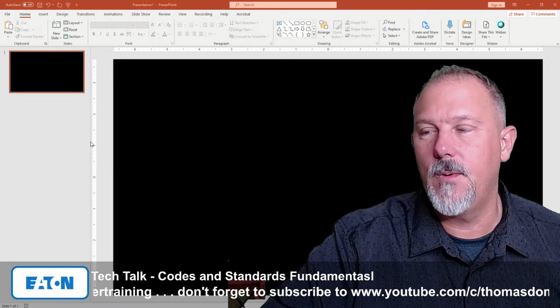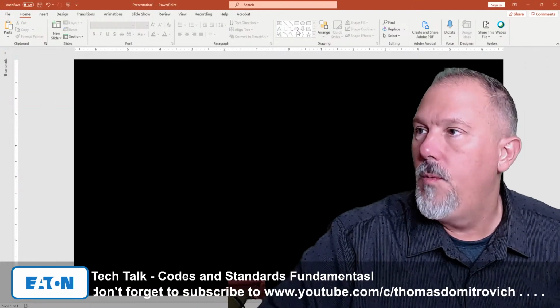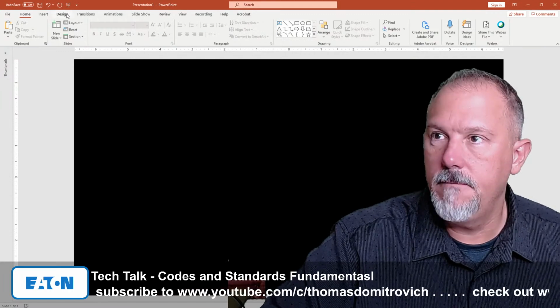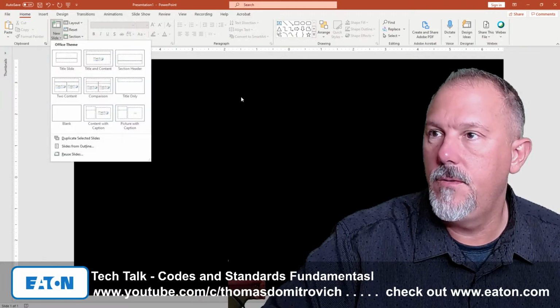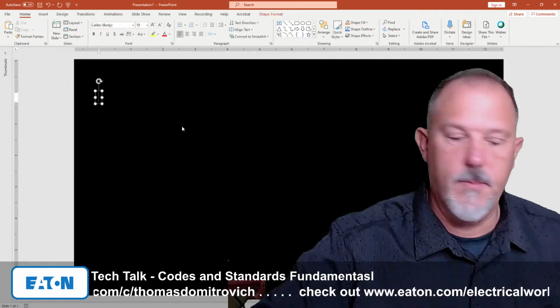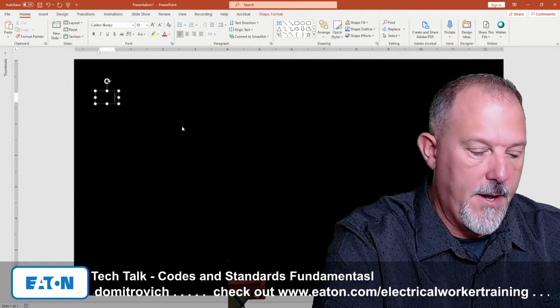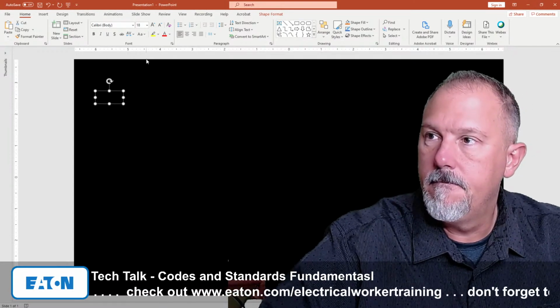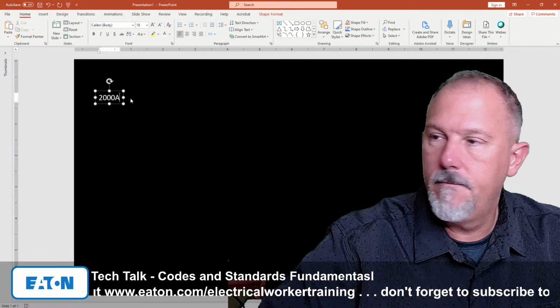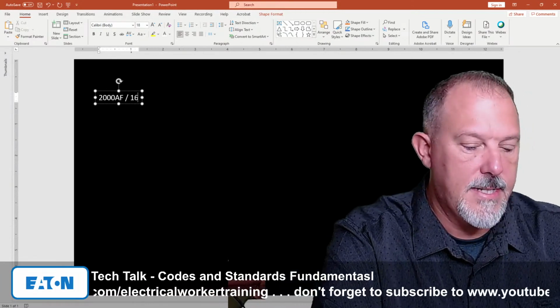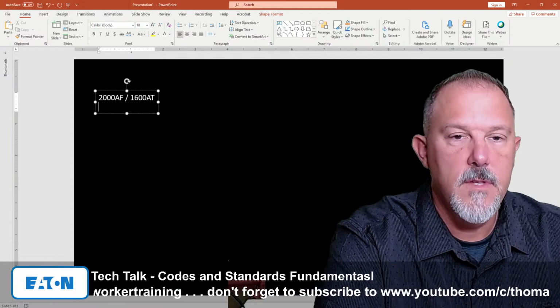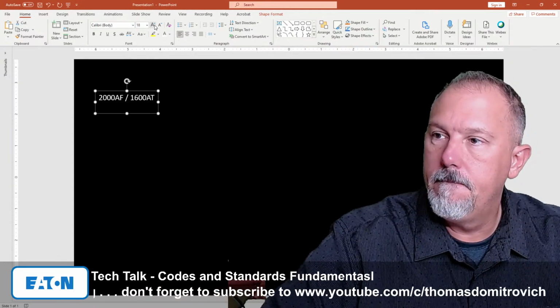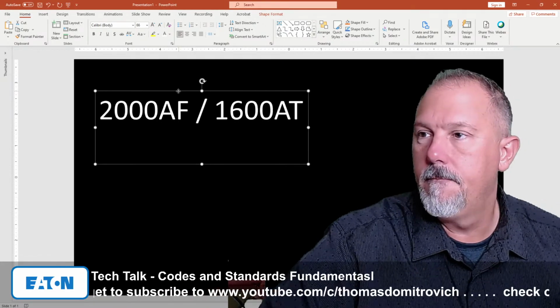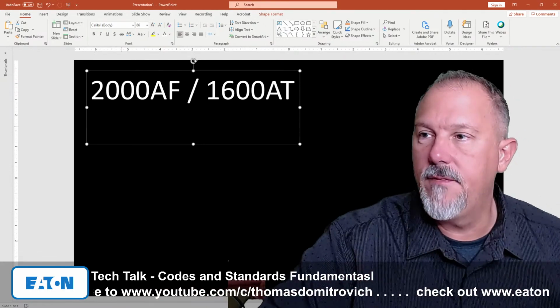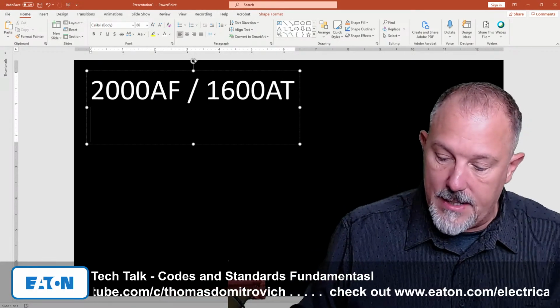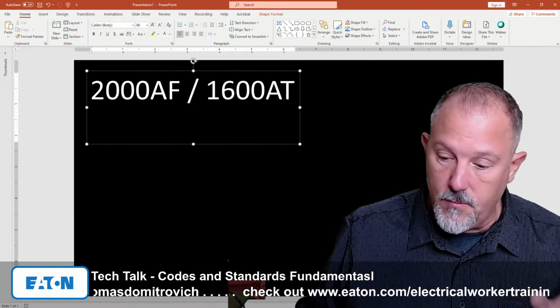Okay, so here's what we have. We have a 2000 amp circuit breaker. I'm going to insert a text box. So I have a 2000 amp frame breaker, and I have a 1600 amp trip. All right, so I have a 2000 amp frame breaker and 1600 amps trip.